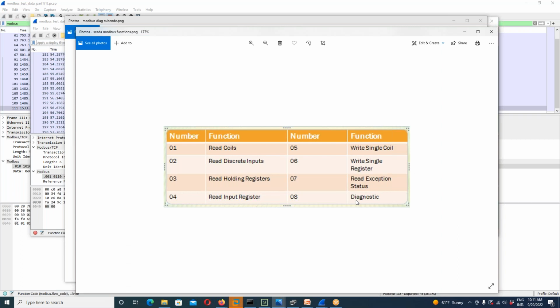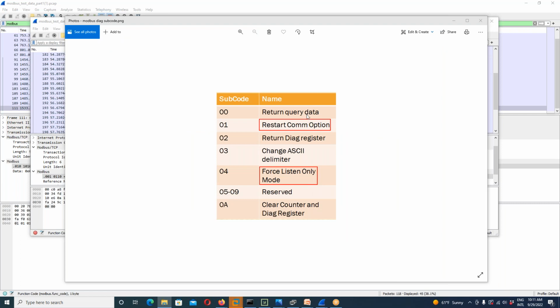Diagnostics is important because it includes subcode 4, which can be used to stop a PLC essentially. And then these are the subcodes of that code. Force listen only was one of the first attacks against Modbus. So early on, we started seeing attacks against this, used to just stop the PLCs. And of course, once I stopped the PLCs, who knows what's going to happen? The whole system is going to fall apart at that point.